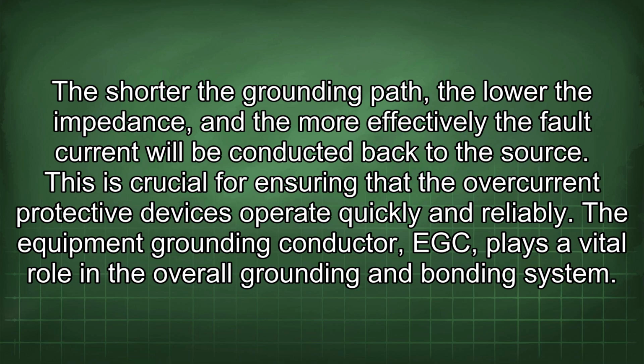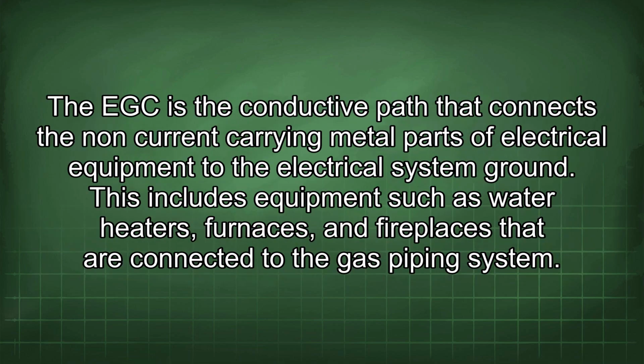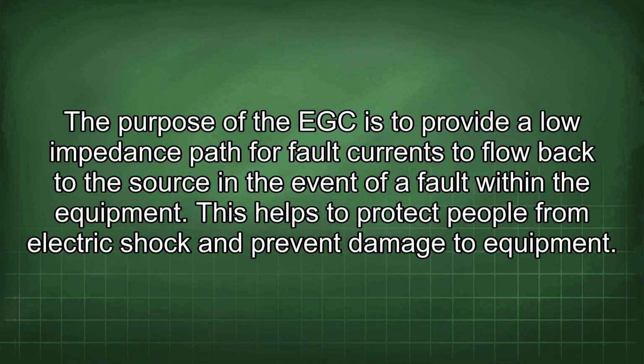The equipment grounding conductor, EGC, plays a vital role in the overall grounding and bonding system. The EGC is the conductive path that connects the non-current carrying metal parts of electrical equipment to the electrical system ground. This includes equipment such as water heaters, furnaces, and fireplaces that are connected to the gas piping system. The purpose of the EGC is to provide a low impedance path for fault currents to flow back to the source in the event of a fault within the equipment. This helps to protect people from electric shock and prevent damage to equipment.